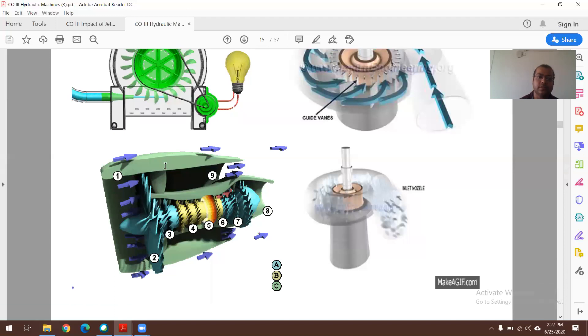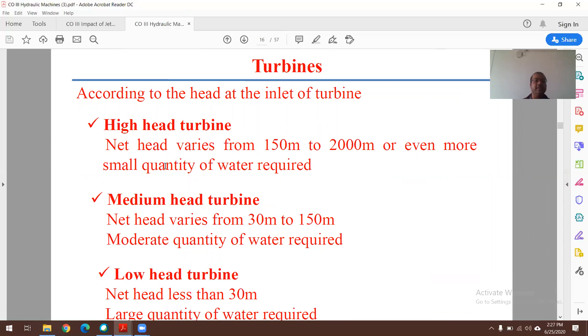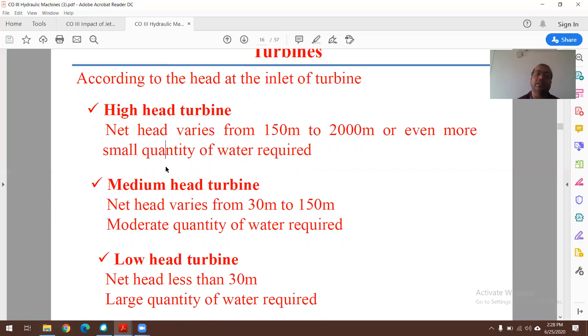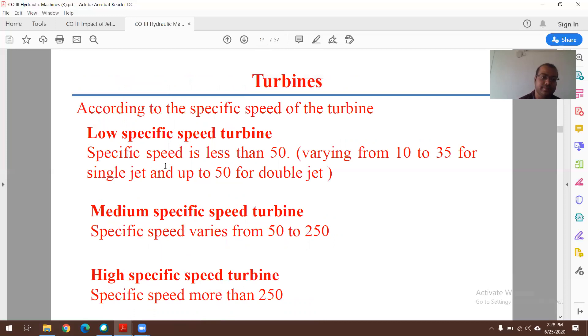Turbines can also be classified based on head: high head, medium head, and low head. High head turbines operate in the range of 150 to 2000 meters or more, requiring a small quantity of water. Medium head turbines operate from 30 to 150 meters, requiring a moderate quantity of water. Low head turbines operate at less than 30 meters but require a large quantity of water. Based on these conditions, a particular type of turbine is selected or designed.